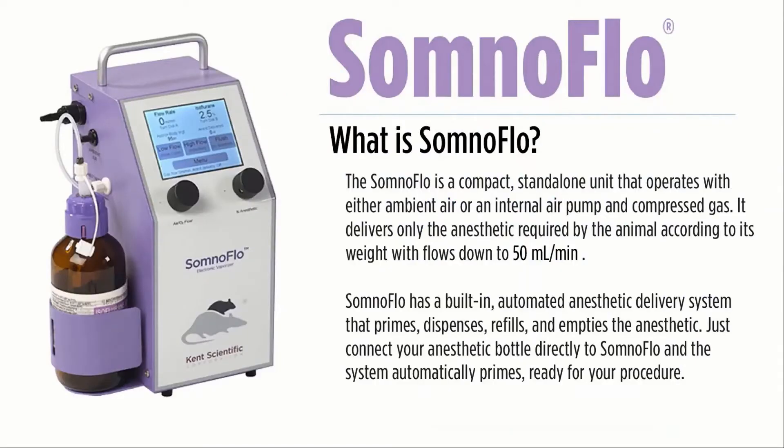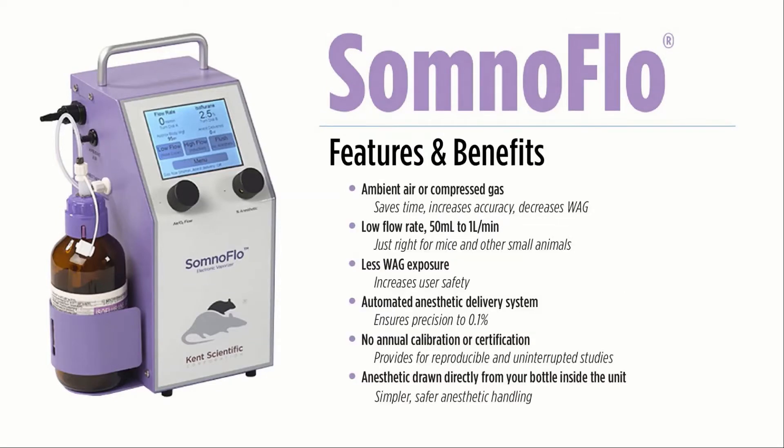The SomnoFlo, however, is different. It's a digital low-flow electronic vaporizer. It's small and compact, weighing less than six pounds, and can be placed anywhere in your laboratory. Not only is it compact and lightweight, it also requires no compressed gas source, utilizing room air or compressed gas should your experiment require it. With airflow rates as low as 50 ml per minute, your exposure is significantly decreased, and your use of isoflurane is also decreased.